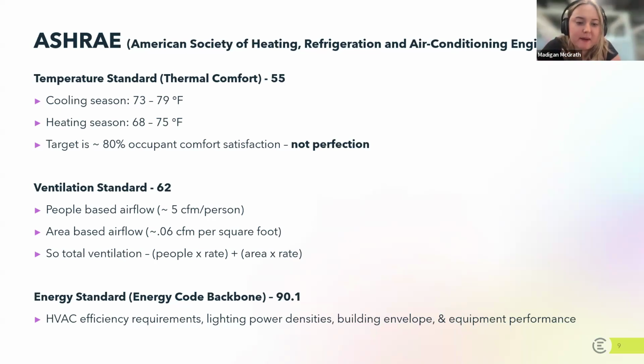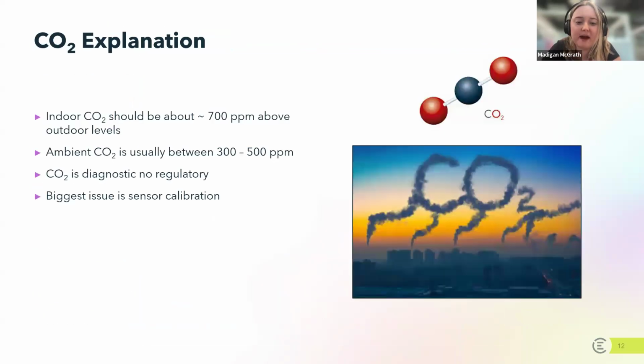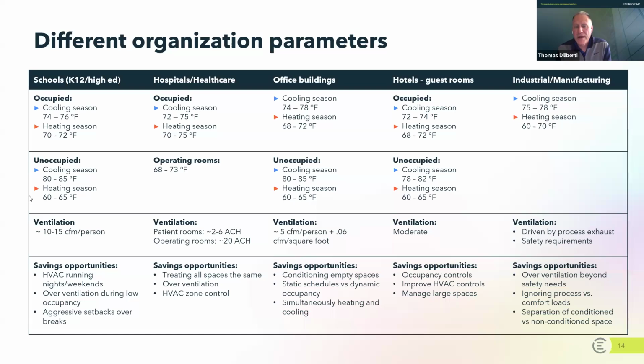The last question is about setbacks on unoccupied set points - do most HVAC systems turn completely off or mainly just setback airflow and temperatures? It's different depending on the system. What we're talking about now is during the heating season. For many systems, suppose you have a setback of 60 degrees Fahrenheit in a school. If occupied temperatures are 70 and students go home, the building goes into a shutdown or unoccupied mode, meaning temperatures coast from 70 down to 60, and the system sustains itself at that set point, so it won't get colder than 60.